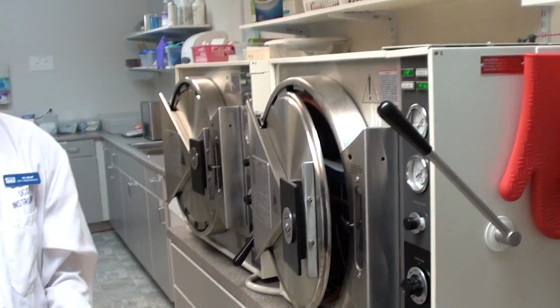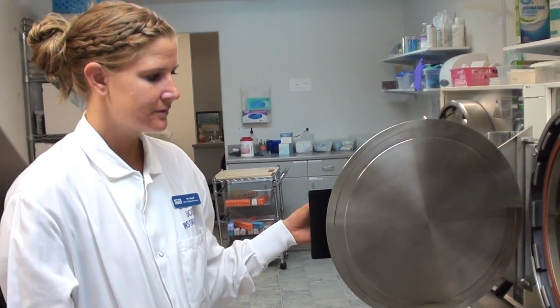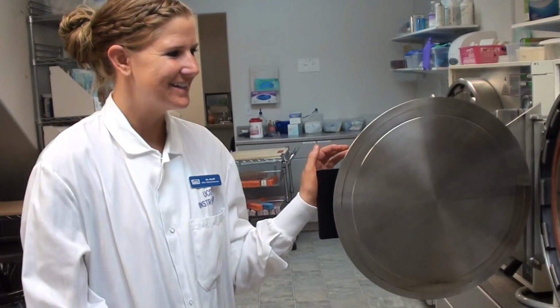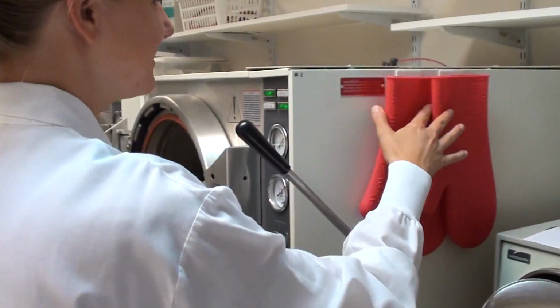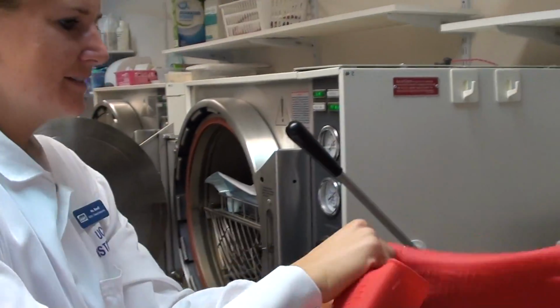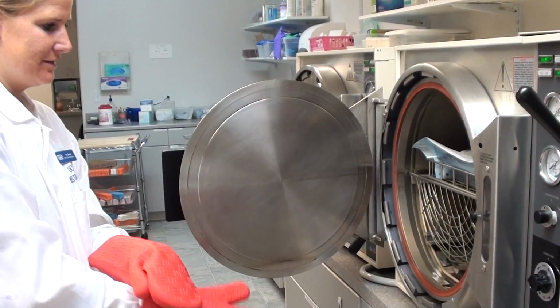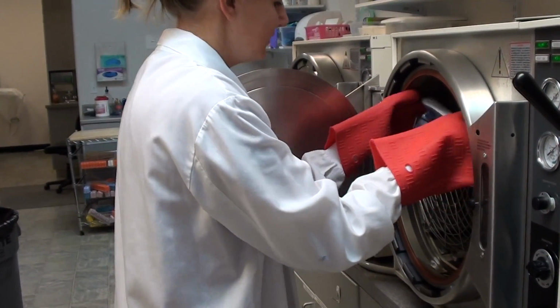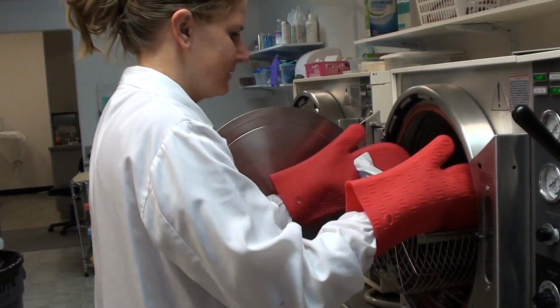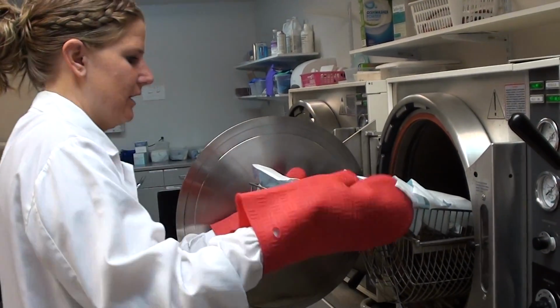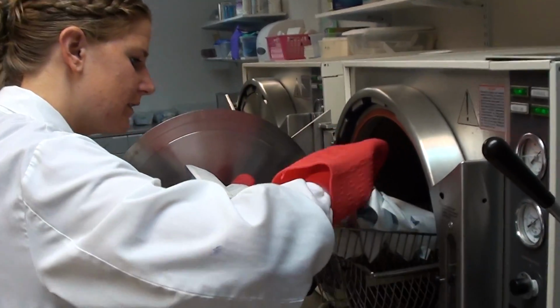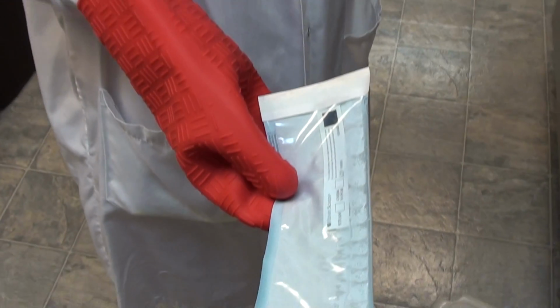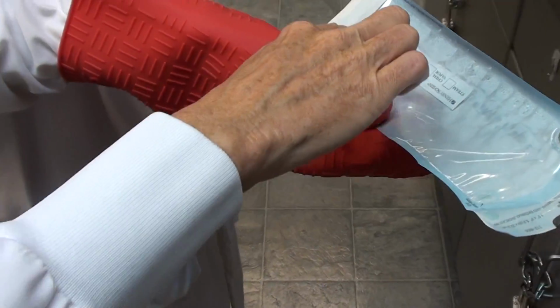A CI must remove and inspect the integrator strip. If no color changes occurred, do not release the load as items in the load need to be reprocessed. So it's been sitting there for 15 minutes. She's the CI. We're going to look for the strip. There's the integrator strip. It's turned black.